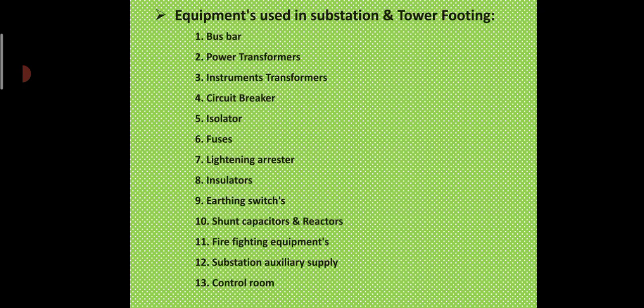For important equipment, station type lightning arresters are used. Arcing horns or rod gaps are used for less important insulations. For example, transformer insulation should be protected by a lightning arrester, while the transformer bushing insulations may be protected by a rod gap, and an isolator may be equipped with an arcing horn.